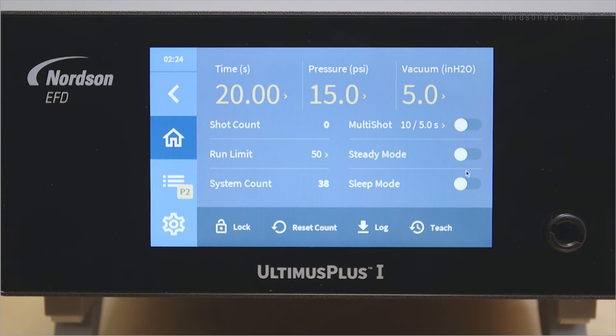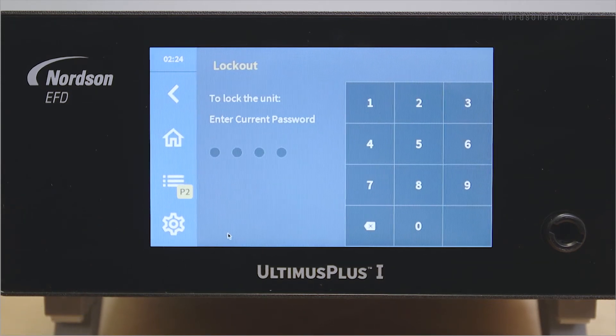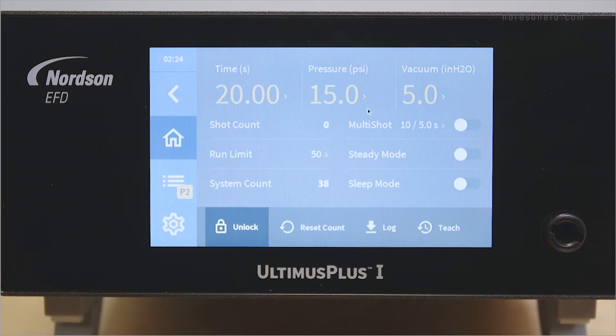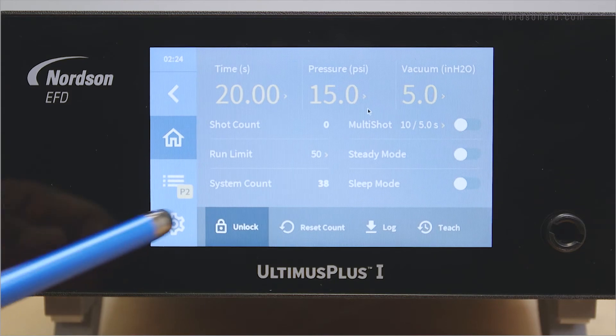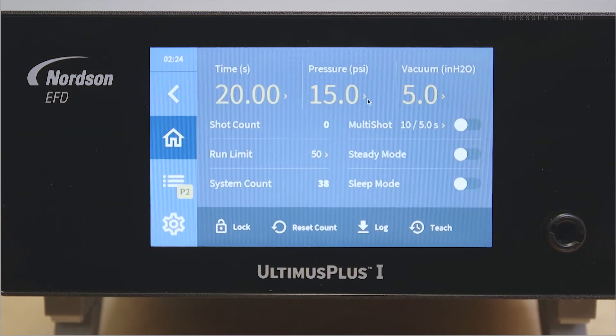The lock functionality will lock out the UltimusPlus to prevent any unwanted changes to your settings. To lock the dispenser, press the lock button. The default password to lock the dispenser is 1111. Once you enter the password, the system automatically returns to the home screen with all options grayed out. To unlock the system, press the unlock button and enter the four-digit password. The default password is 1111.